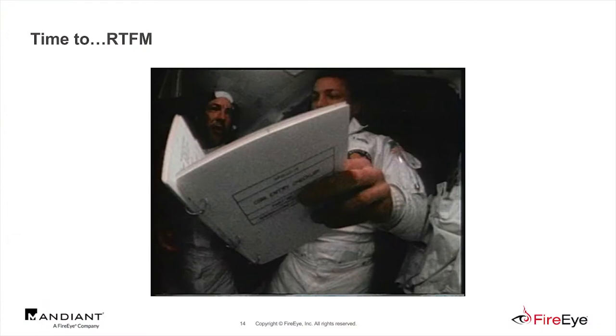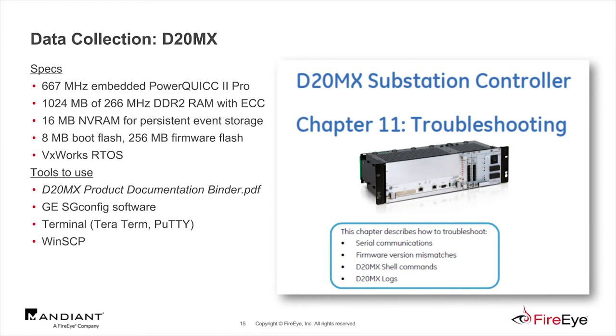Let's do some DFIR on two example substation RTUs. Your devices may be completely different, but this methodology is what we want to start sharing as people do more research. Read the manual — just like Apollo 11, they had manuals for everything. The first one is a GE D20MX. It's the newer version of the older D20, with a PowerPC processor, a gig of RAM, and VXWorks real-time operating system. Tools to use: the manual, SG Config software, terminal like Teraterm or PuTTY, and WinSCP. Chapter 11 covers troubleshooting — serial communications, firmware mismatches, shell commands, and logs.